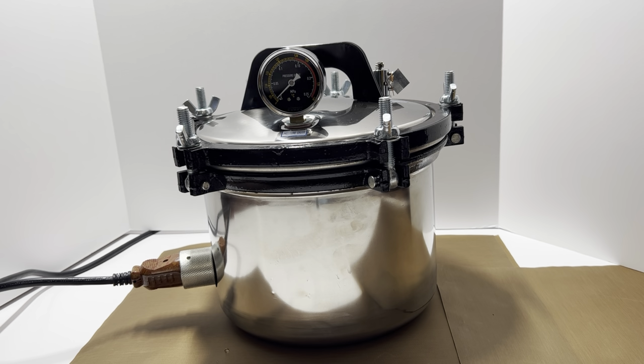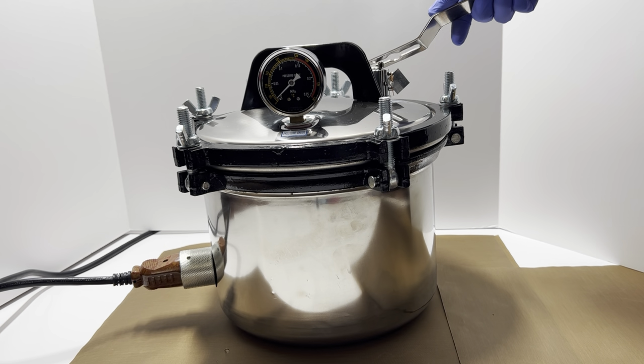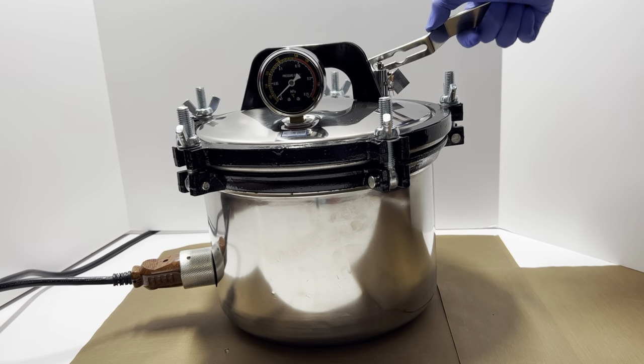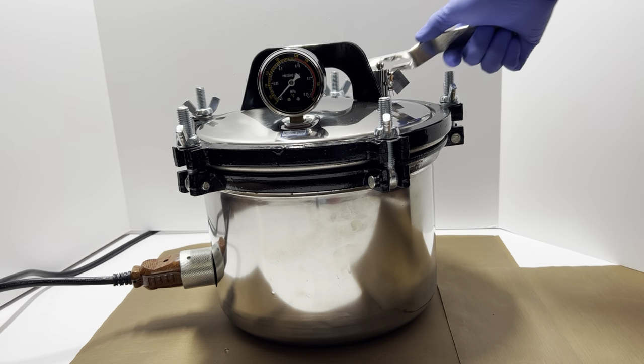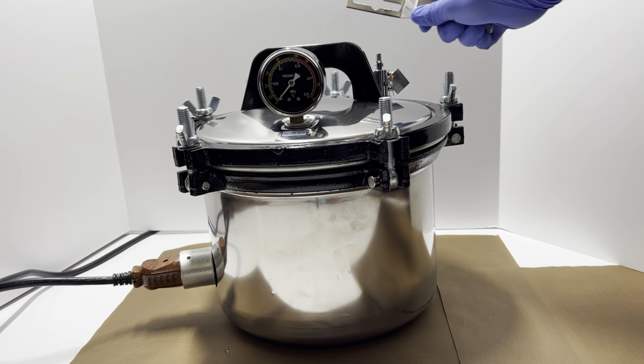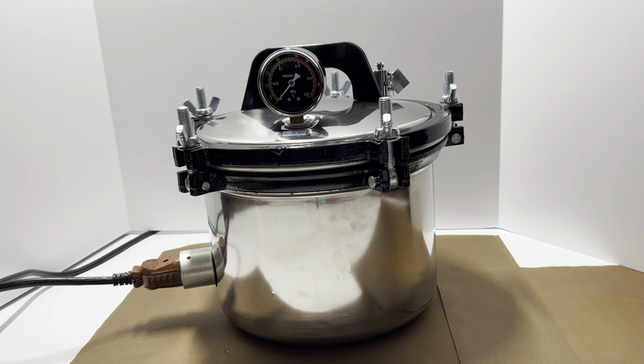Okay, so when I start seeing the gauge move a bit, that means the pressure is building up. What I like to do, or what's recommended, is to let the cold air or the cold steam that was there from before completely out like so, and then allow the steam to build up again. So that's how I approach it, that's what I'm going to do.